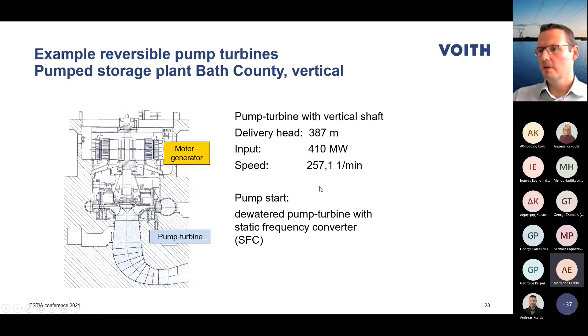So these pump turbine solutions with fixed speed have certain topics, as said, where they have limitations. So variable speed pump turbines come into consideration. There are some disadvantages also for variable speed pump turbines because they have a high investment cost and also a larger complexity, which means in the end some more servicing and maintenance efforts.